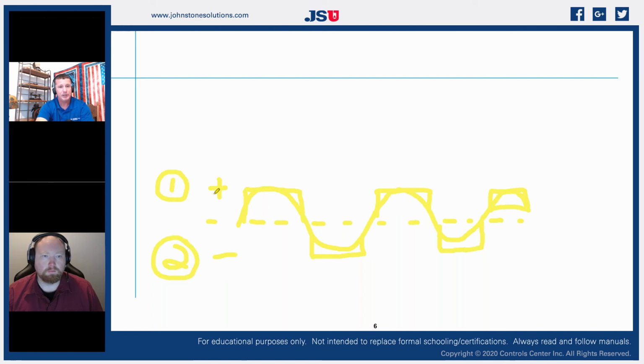But there's going to be a difference between them, because remember, if Daikin says on theirs, typically from ground to 1, we're going to have about 2.8 volts DC positive, and from ground to number 2, we're going to have around 2.2 volts DC in reference to ground. So total voltage, our whole bandwidth is about 5 volts DC, because we were just splitting up a 5 volt DC signal, putting a ground in it, going above, and then going below. Well, if we put our meter on that, we're not going to see 5 volts DC. We have a positive 2.8 and a negative 2.2. That's going to leave us with a difference of 0.6 volts DC.